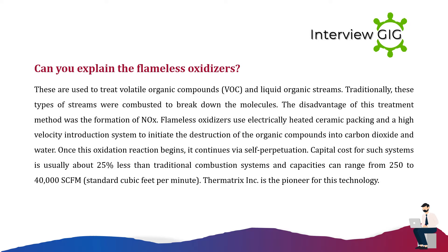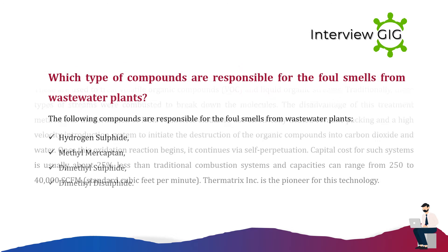Can you explain flameless oxidizers? These are used to treat volatile organic compounds (VOC) and liquid organic streams. Traditionally these streams were combusted to break down the molecules, but the disadvantage was the formation of NOx. Flameless oxidizers use electrically heated ceramic packing and a high-velocity introduction system to initiate the destruction of organic compounds into carbon dioxide and water. Once this oxidation reaction begins, it continues via self-perpetuation. Capital cost is usually about 25% less than traditional combustion systems, with capacities ranging from 250 to 40,000 SCFM. Thermatrix Inc. is the pioneer for this technology.